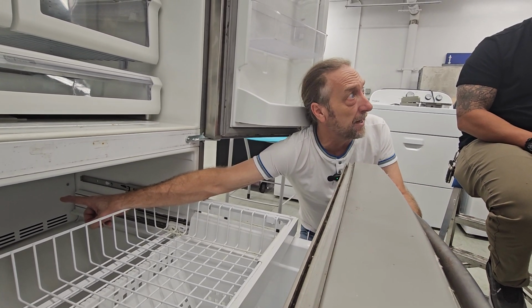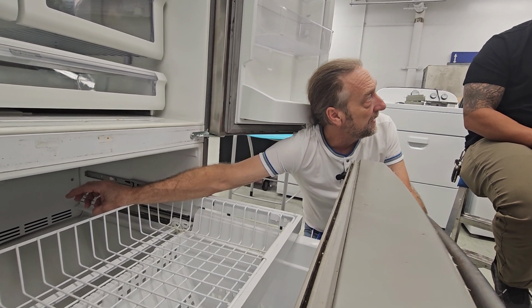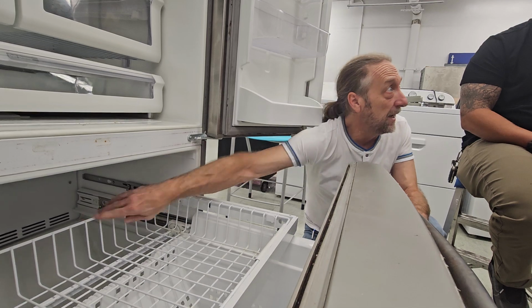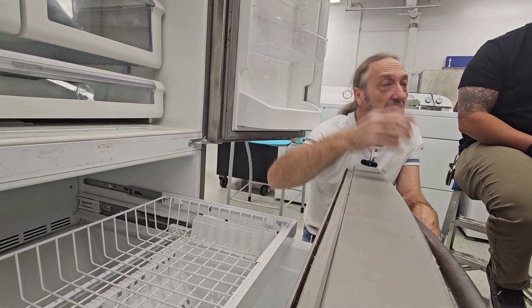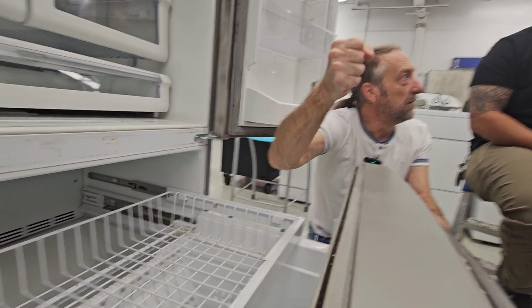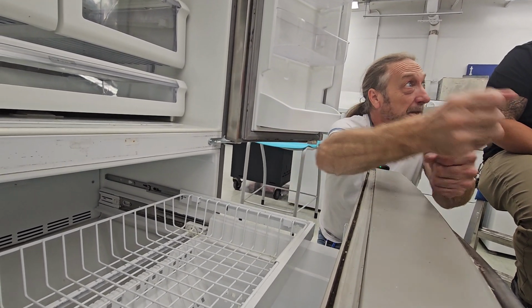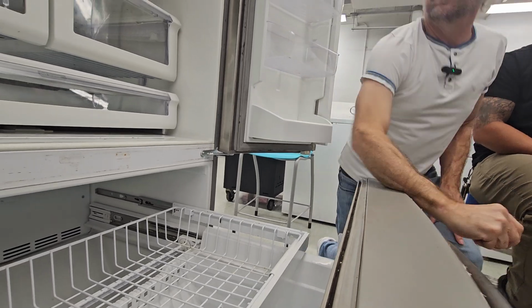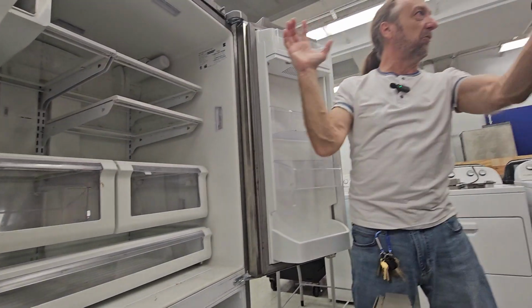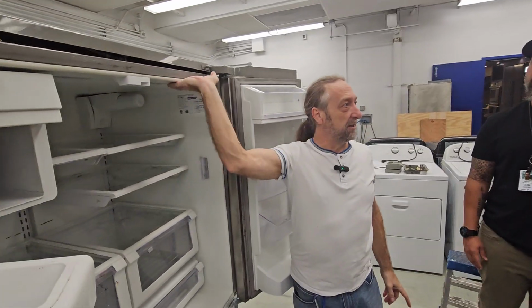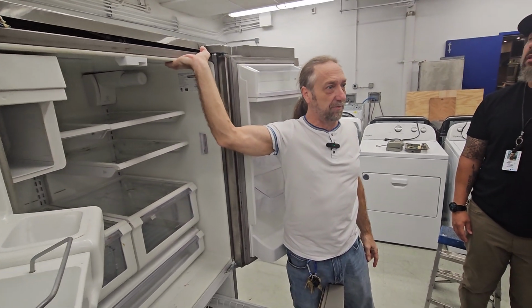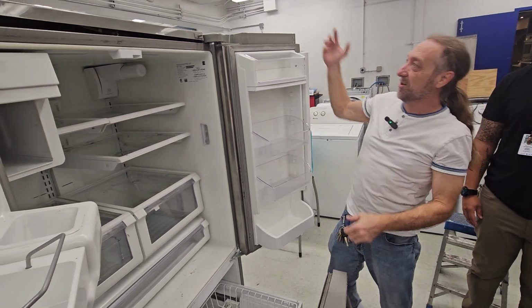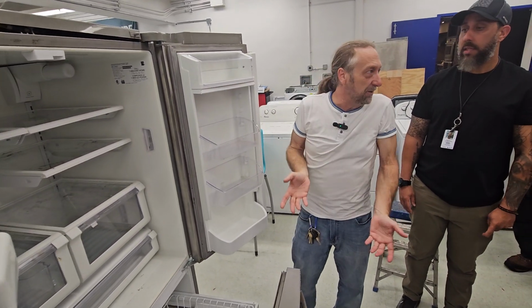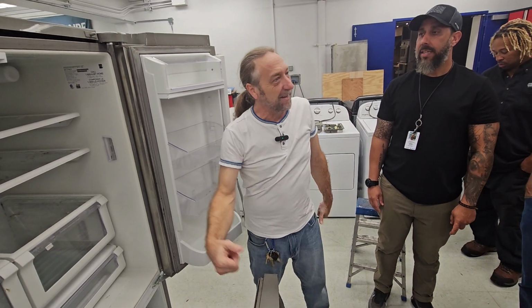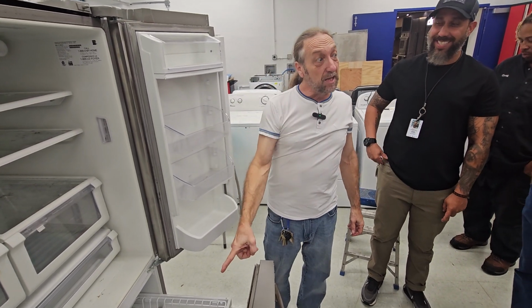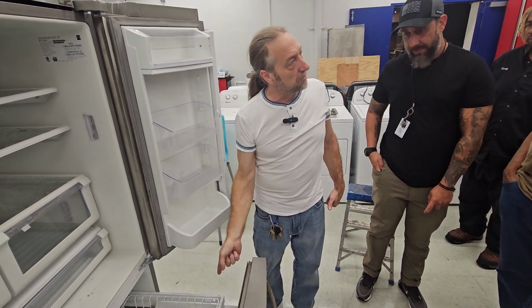I've seen an Avanti refrigerator back in the 90s when I was working at BrandSmart, and they were joking with me - I went into the shop with a top freezer, and they said, open the freezer. So I grabbed the door and the whole refrigerator started moving, and they were laughing at me. So I grabbed the handle and ripped it, and this plastic liner in the freezer had melted because it went into defrost and the heater didn't shut off. When I ripped it, I tore the plastic off the door. It was garbage anyway, but they were laughing at me, then I laughed at them - I got it open. So that was the evaporator sensor, but there's another sensor in there called the freezer sensor.